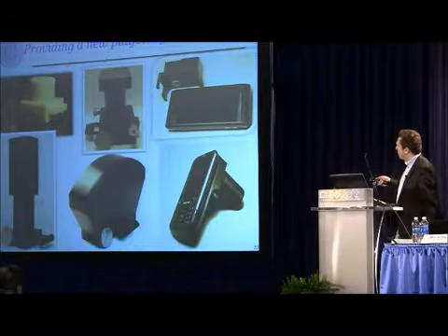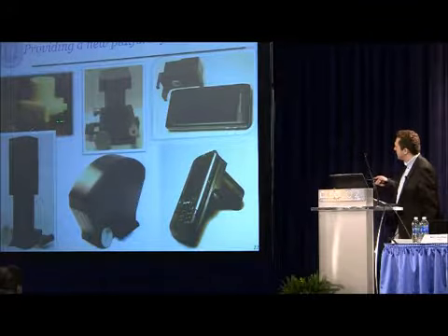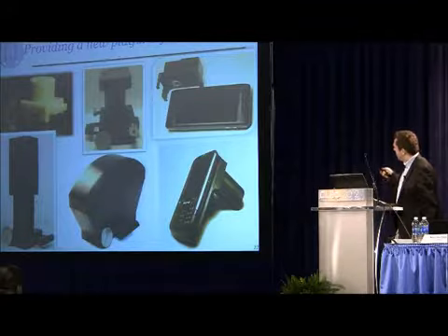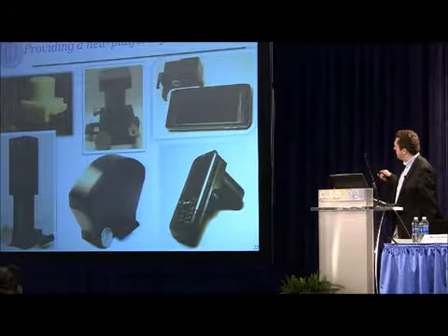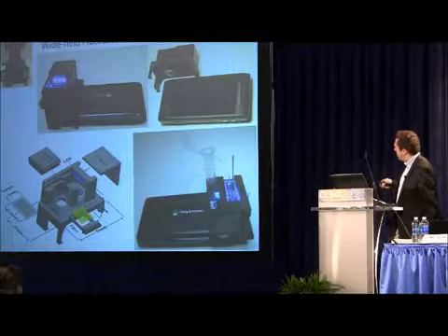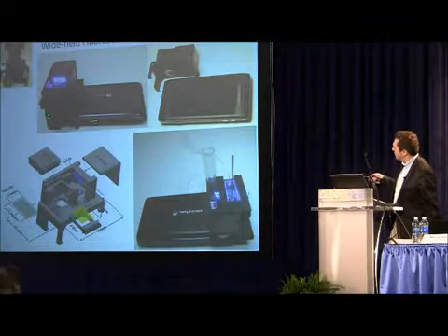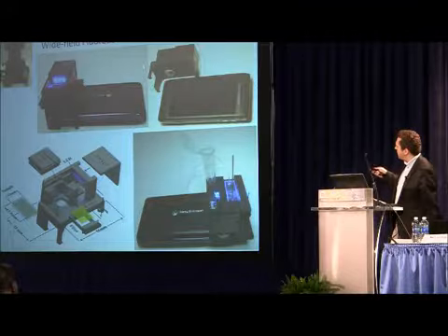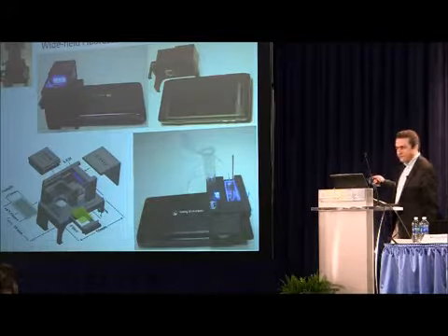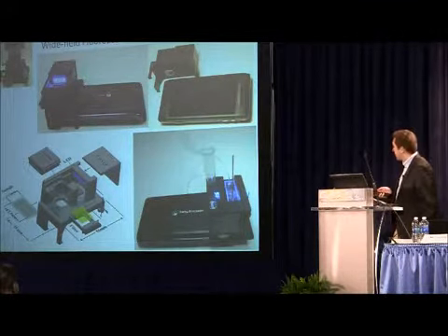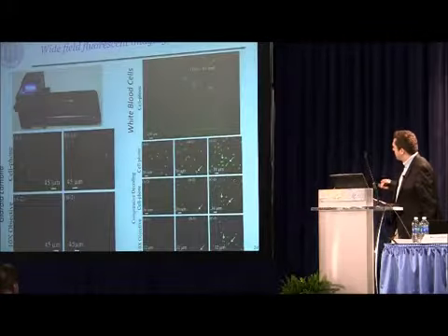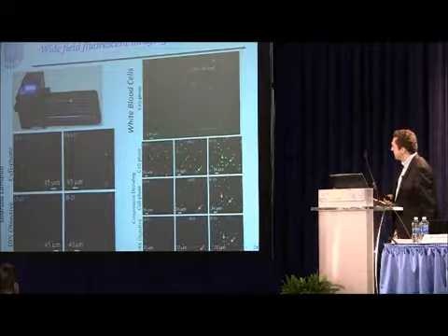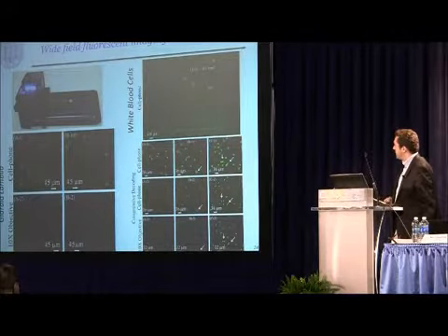So what I've shown you so far were mostly transmission microscopic images acquired with these partially coherent sources, but you can also do fluorescent microscopy on a cell phone. And this one actually is a fluorescent microscope which looks at a very large area, installed at the back of a cell phone camera unit. It's a very compact unit, on the order of a matchbox, with less than 30 grams. And this is a flow cytometer in the sense that it can look at specimens while they're flowing and then understand the density of the white blood cells or other things.